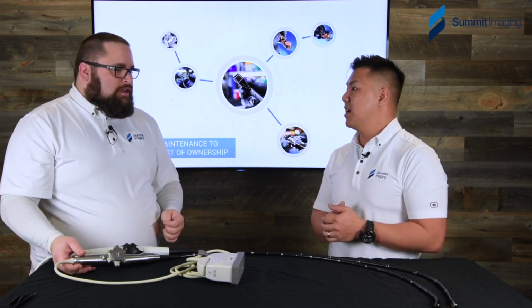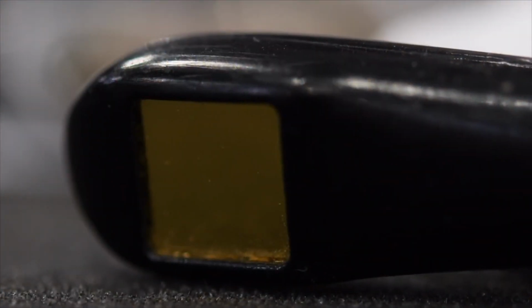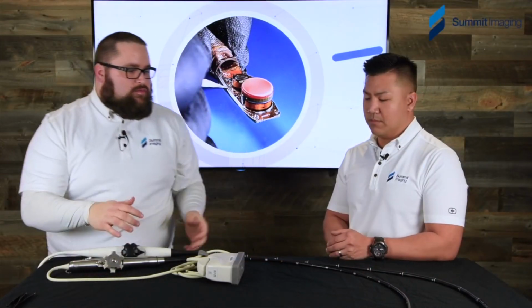And quite frankly, even though the patient's under anesthesia, it can't be comfortable having this thing dragging 90 degrees up the entire esophagus. Yeah, just like the fish we caught when we were kids. You got to be kind of nice to it, otherwise it's never going to come back, right? Yeah. On top of that, things that happen in the OR, like, okay, we need to pull it, we need to go fast, and they're just placing it over the control panel of the machine and just letting that array tap the side. Yeah. Doesn't seem like much when everything else in that room is titanium, but when you have this little crystal right here and it just hits the side of a cart, it cracks, and it's gone. So there's lots of room for improvement even in the OR.